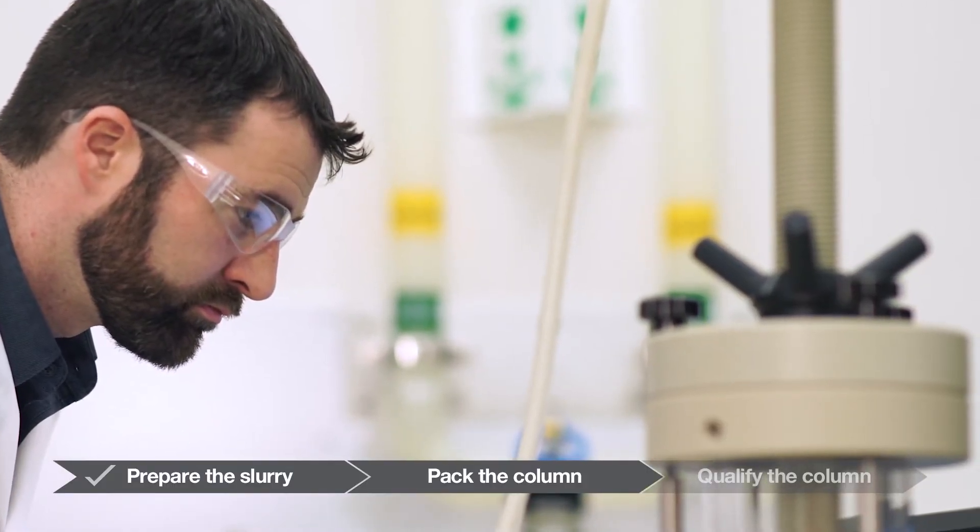Change the valve back to flow through the system on the top and open the column bottom. To initiate flow, start the chromatography system pump. Increase the flow rate to the maximum or desired flow rate and pressure obtainable with the equipment used. While adjusting the flow rate and forming the bed, you may observe some turbidity in the effluent as packing begins. This will clear as packing proceeds and one to two bed volumes of packing buffer pass through the column. The bottle on the left was sampled at the start of the pack and the bottle on the right was sampled towards the end of one column volume. Continue flow until a clear space forms between the column top adjuster and the slurry, approximately two column volumes. Monitor the pressure. It will gradually rise as the column packs. Reduce the flow rate if the packing pressure approaches the system pressure limit.